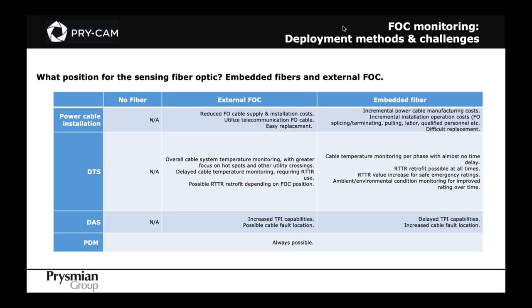This increases TPI capabilities when using external fiber optic cables, and can be used to locate cable faults. There is a delay in TPI capabilities when using embedded fibers, but increased value with cable fault location. Partial discharge monitoring is always possible, whether the fiber is outside, inside, or without fibers.